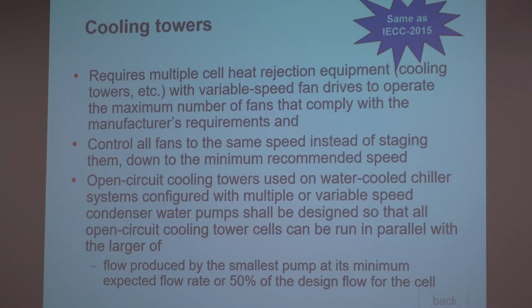For cooling towers, the big change here is that we're wanting you to run them a certain way. So when you have multiple cells, we want you to run the maximum number of cells at the same fan speed. This gives you effectively a larger surface area, which makes your cooling tower more effective. We also want to make you have some good flow turndown. If you have the ability to turn a cooling tower cell down to 50% of its flow on the water side, that means you can flow one chiller over 2 towers, and that makes your tower more effective as well. So those kinds of provisions are going to change the way we operate and maybe even select and design our cooling towers.